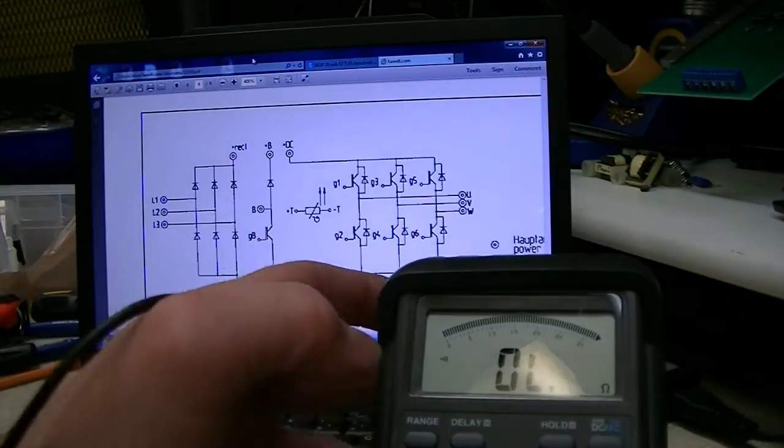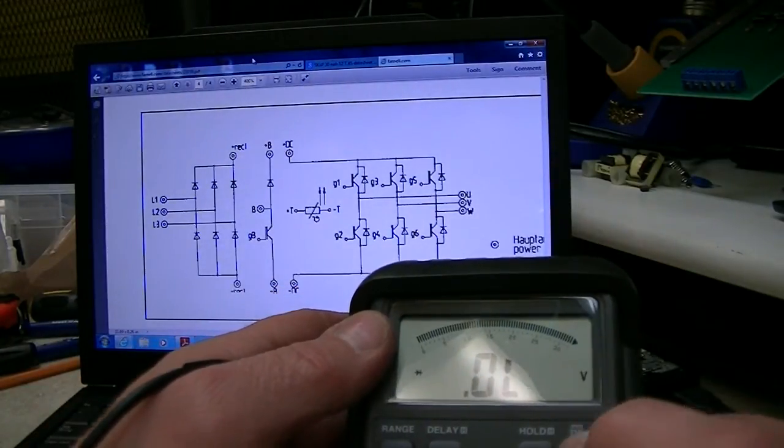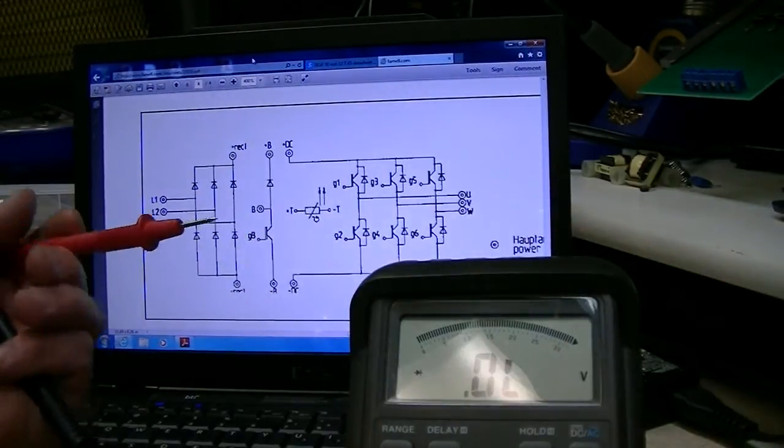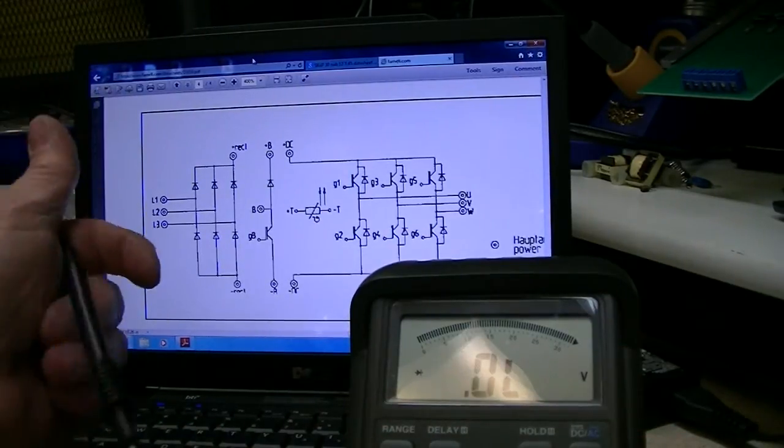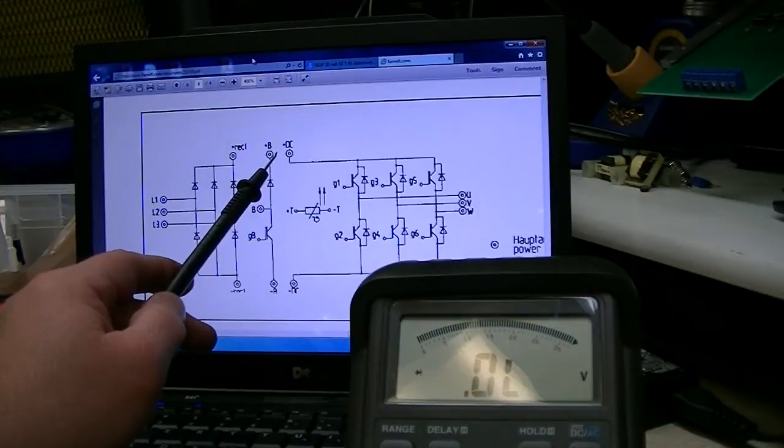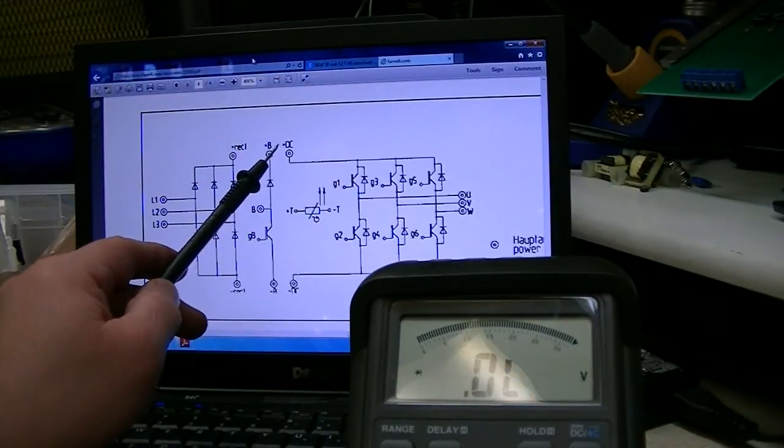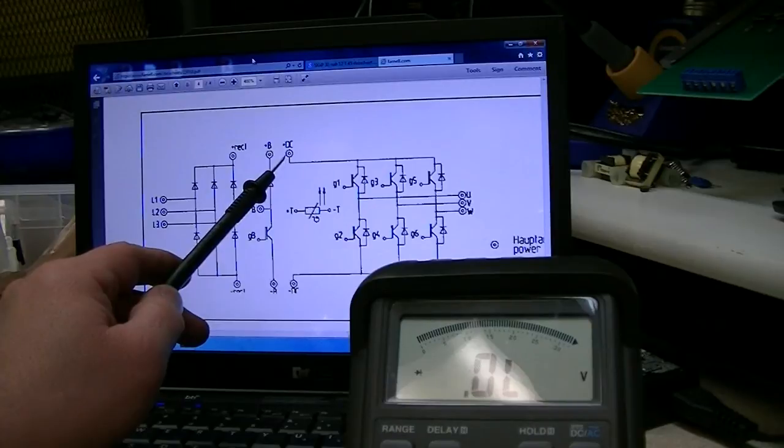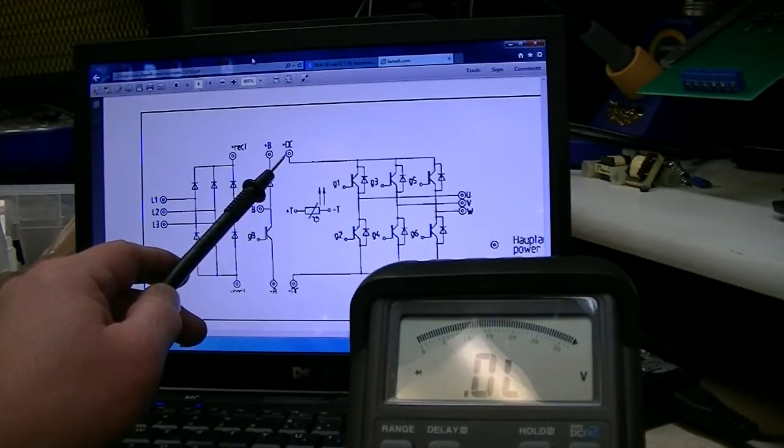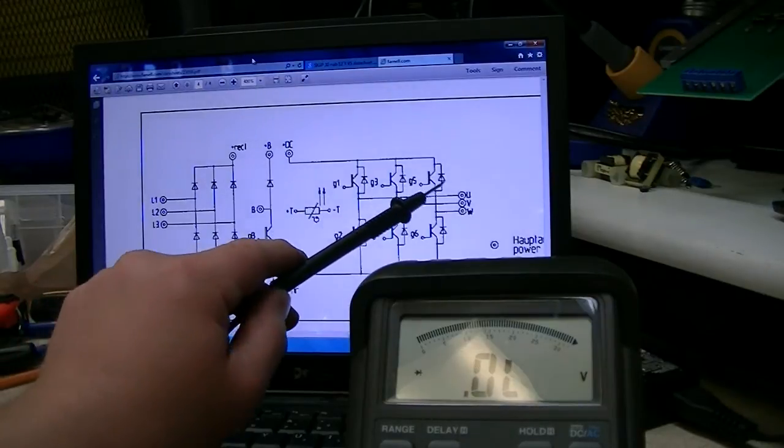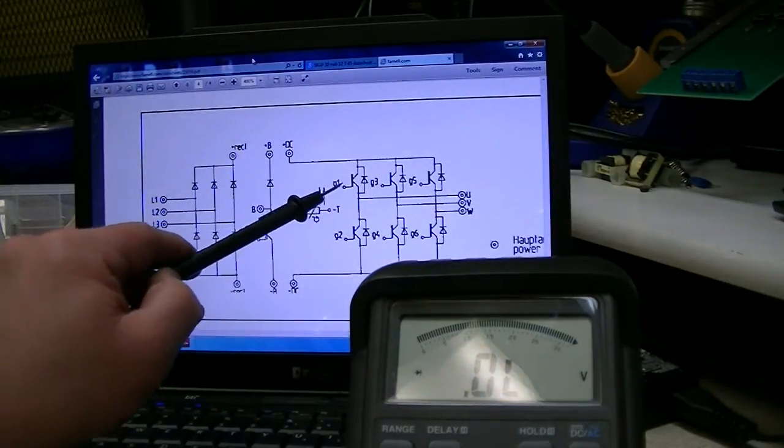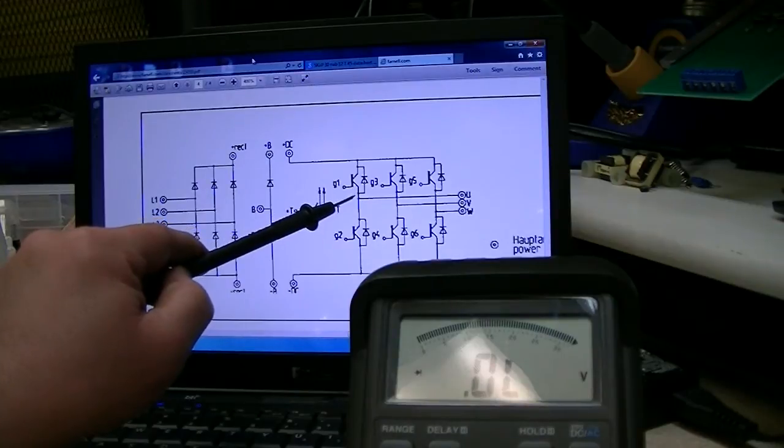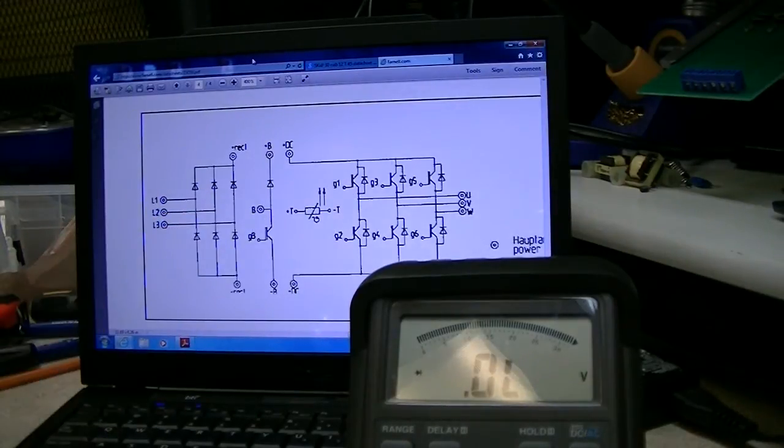So I'll go back on the diode function. So next up, we can go across each one of these IGBTs. We go to DC, I'm assuming DC plus. And we can go UVW and then swap leads around. And we should have blocking in one direction. Then we should have a diode drop in the other direction.